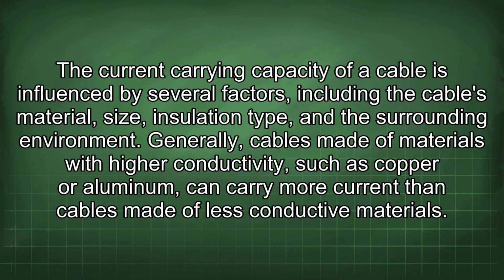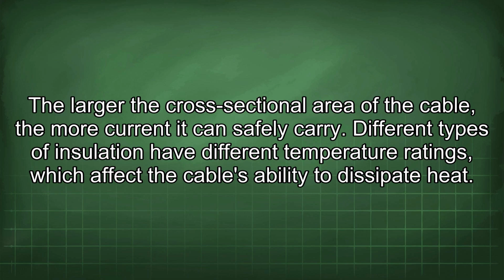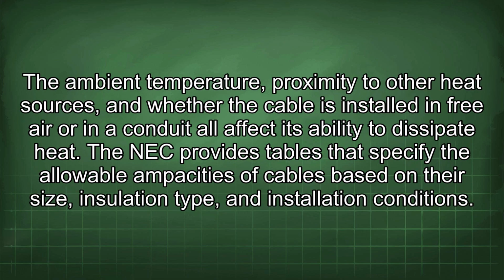The current carrying capacity of a cable is influenced by several factors, including the cable's material, size, insulation type, and the surrounding environment. Generally, cables made of materials with higher conductivity, such as copper or aluminum, can carry more current than cables made of less conductive materials. The larger the cross-sectional area of the cable, the more current it can safely carry. Different types of insulation have different temperature ratings, which affect the cable's ability to dissipate heat. The ambient temperature, proximity to other heat sources, and whether the cable is installed in free air or in a conduit all affect its ability to dissipate heat. The NEC provides tables that specify the allowable ampacities of cables based on their size, insulation type, and installation conditions.